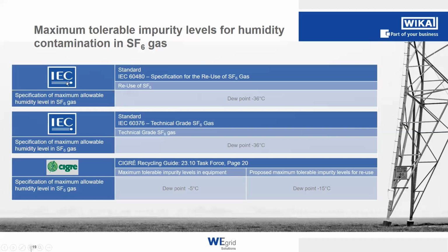And since we talked about the dew point temperature, we have regulations for that. In the IEC, we used to have a difference, but now the dew point temperature for the reuse of SF6, so recycled SF6 gas, is minus 36 degrees, and we also have minus 36 degrees for the dew point with technical grade, also speaking new gas. And then we have a standard specification from the CIGRE as well, which gives us maximum tolerable impurity levels, which then is minus 5 degree temperature for the dew point, and we have a proposed maximum tolerable impurity level for reuse gas, which is set to be a dew point temperature of minus 15 degrees.